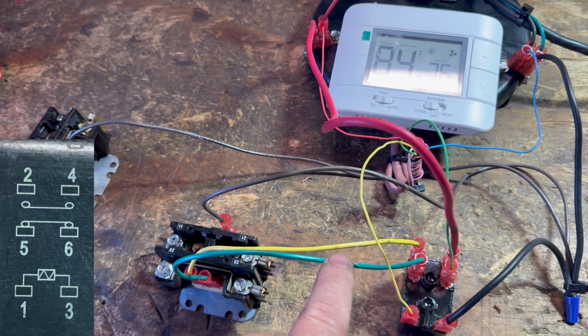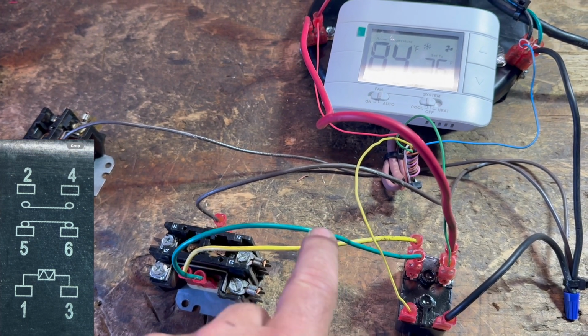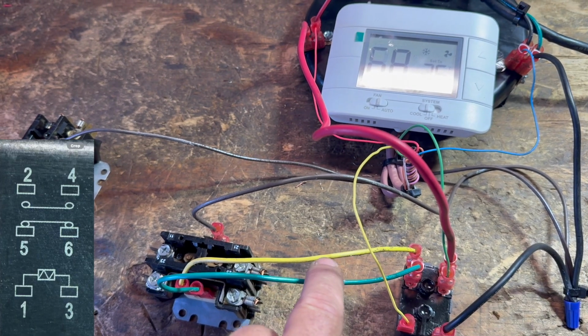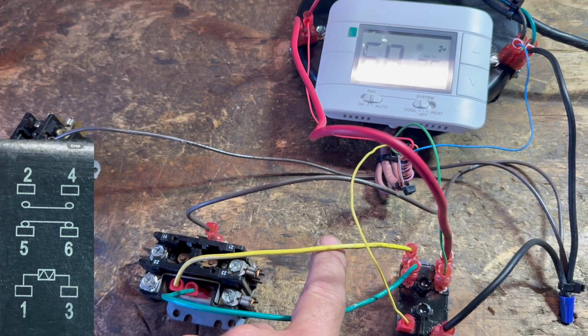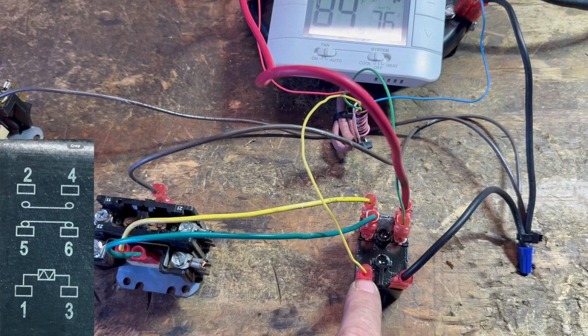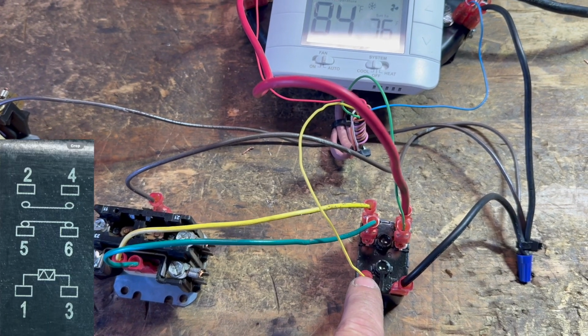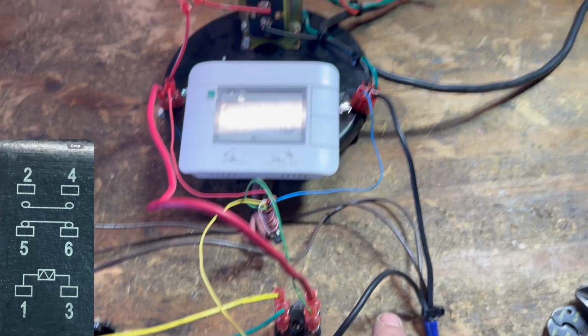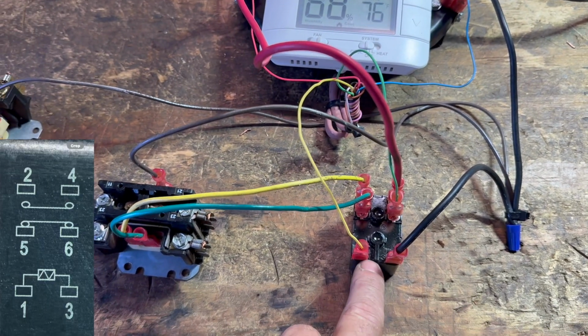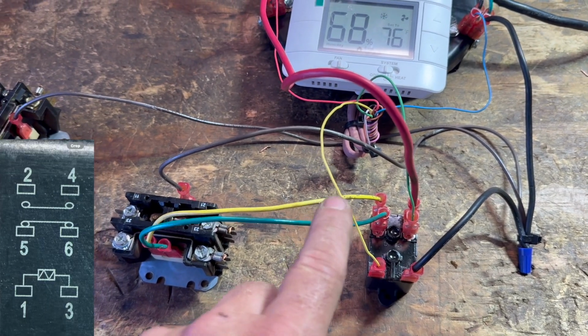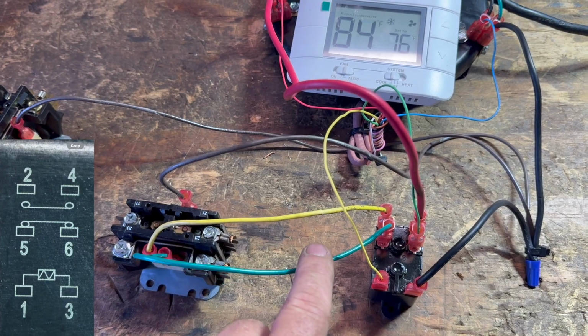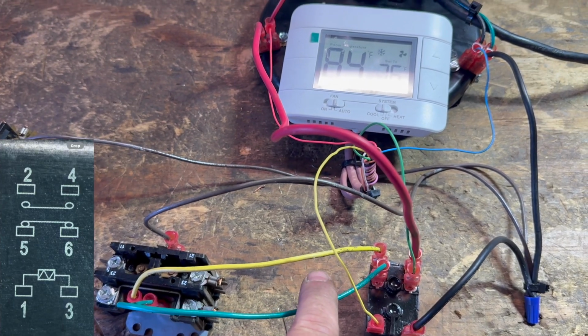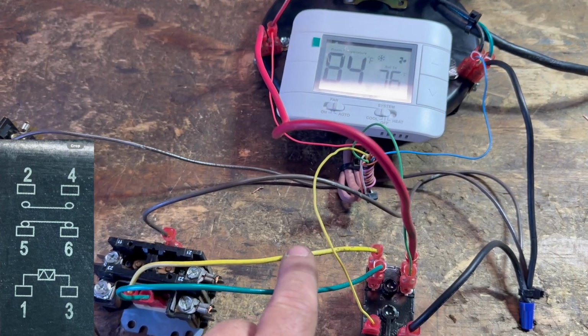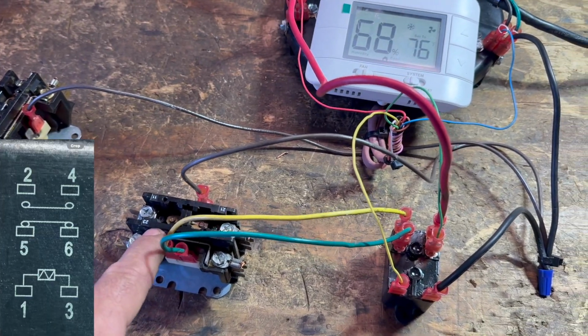Here's the thing, we do not have two 24 volt signals going though. We only have one. Right now it's on yellow because we've activated our relay with a call for cooling from the thermostat on this yellow wire. This other side is just common. It completes the circuit for the load inside here. So there is no 24 volts on this. Right? We don't need it. We use the 24 volts from it telling to put the cooling on to activate the load.